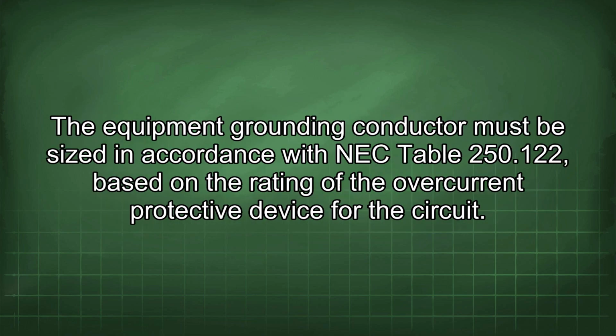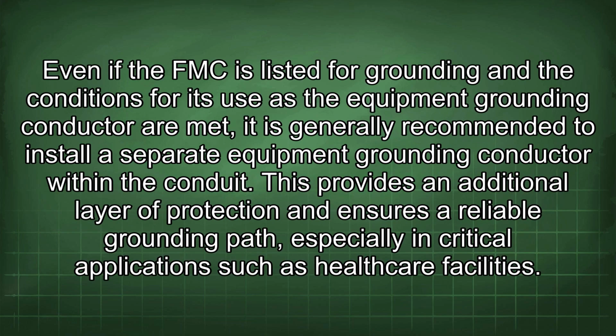The equipment grounding conductor must be sized in accordance with NEC Table 250.122, based on the rating of the overcurrent protective device for the circuit. Even if the FMC is listed for grounding and the conditions for its use as the equipment grounding conductor are met, it is generally recommended to install a separate equipment grounding conductor within the conduit.